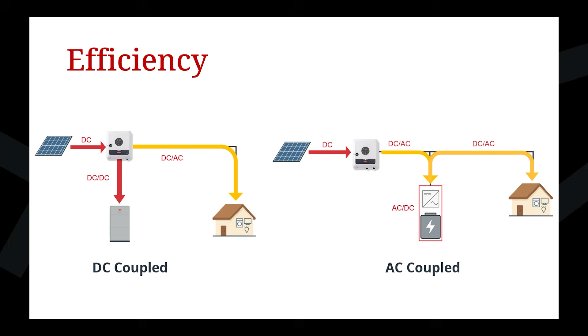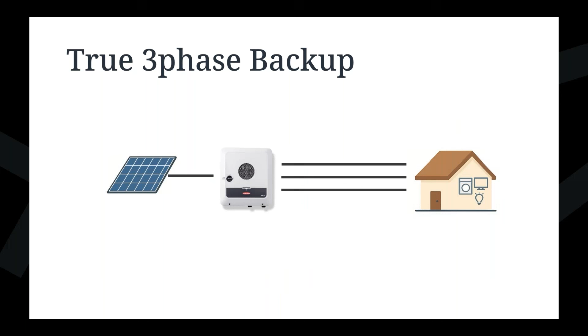Another thing with DC coupled batteries is that you can do true three-phase backup if you've got an inverter that can do that. So both the Primo Gen24 Plus and the Verto Plus can do three-phase backup. So that's true three-phase backup. So for those of you that have three-phase loads, that could be quite important as well, okay?